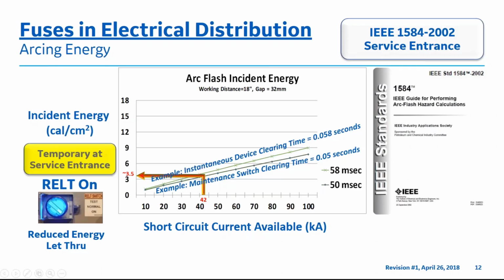During maintenance mode, GE's term is RELT, or reduced energy let through, which is a component with a blue LED switch that is turned on either manually or electronically. During an arcing event at the service entrance location, you will follow the bottom of the orange arrow from the x-axis up to the diagonal line, which represents the clearing time of the electronic device, and you follow it horizontally over to the left, which represents the y-axis, to estimate the incident energy level of approximately 3.5 calories per centimeter squared.